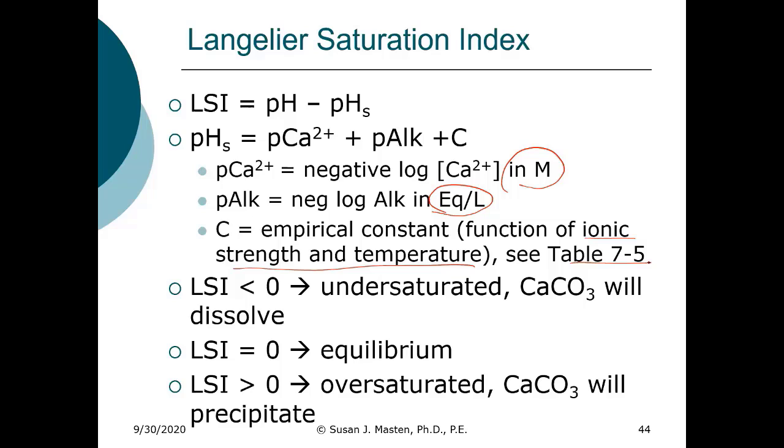If the LSI is equal to 0, then you're at equilibrium, and if it's greater than 0, you're oversaturated and calcium carbonate will precipitate.